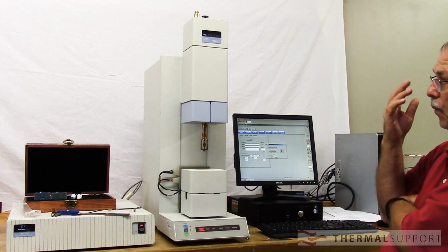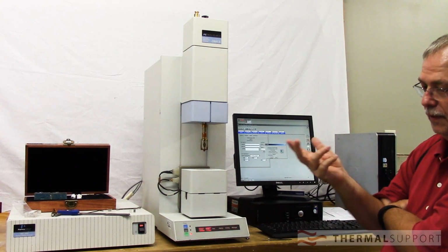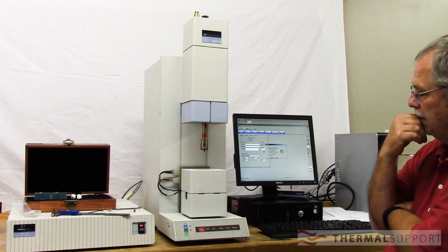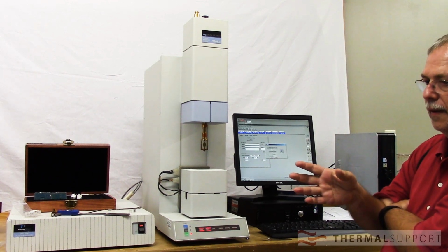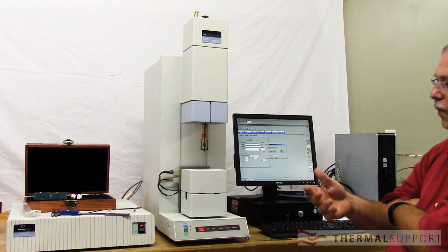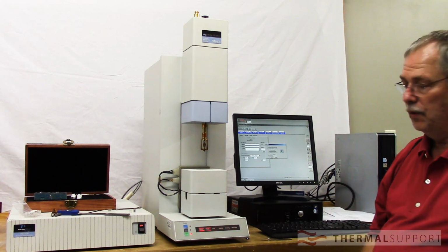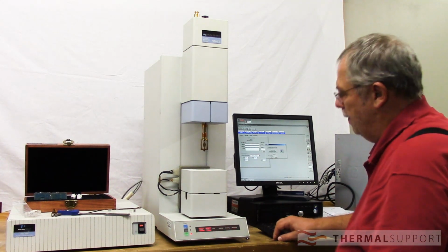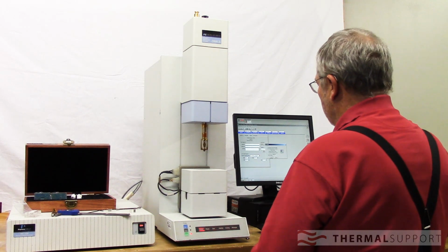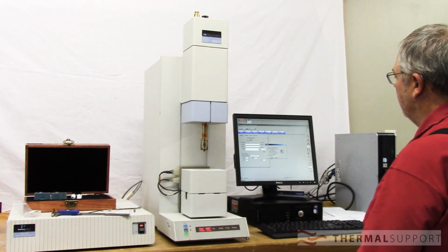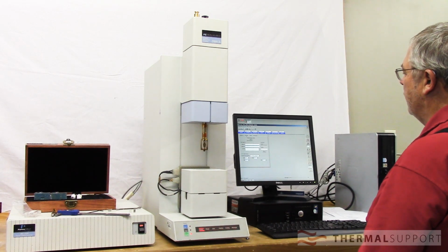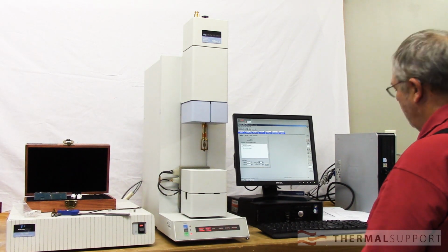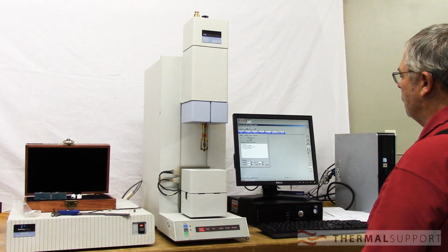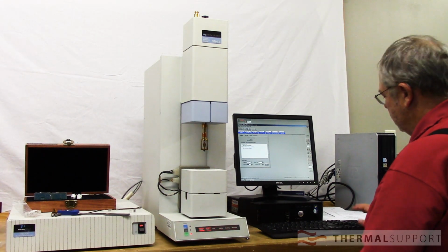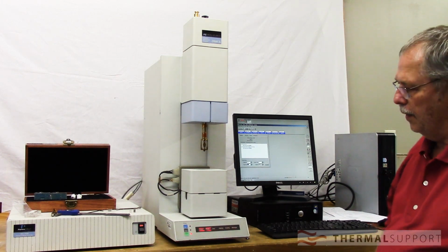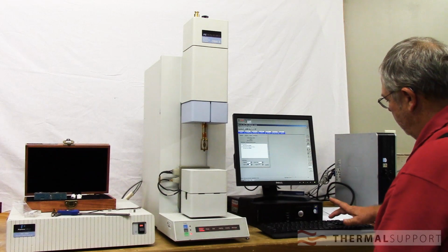Now, the goal here, without a platform, which adds a lot of stuff to the top of this thing that has to lift, it's not supposed to, is to get within 0.1. That's basically what you're looking for. Right now we are half of that, so we're doing pretty darn good. So now that we're here, found my tweezers, we've carried out the probe. We want to find out what the true zero is. So we're going to zero out the dynamic force. And I actually did this a little bit ago, so I know that the true zero is right around here.